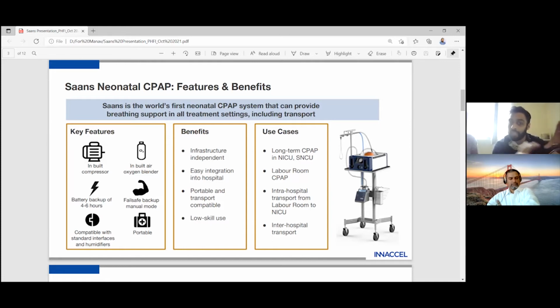This device, the one I've shown, has a manual mode where if electricity is not available, if your battery is drained, you have a manual powering option where you basically pump up that orange balloon you see, you pump it up with an external ambu bag, and then the device will still provide the same CPAP output. And then it's compatible with a whole range of interfaces, humidifiers, and all of that. So the idea is that we've removed a lot of the dependence on infrastructure, because as you can see with this device, you can use it in any setting.